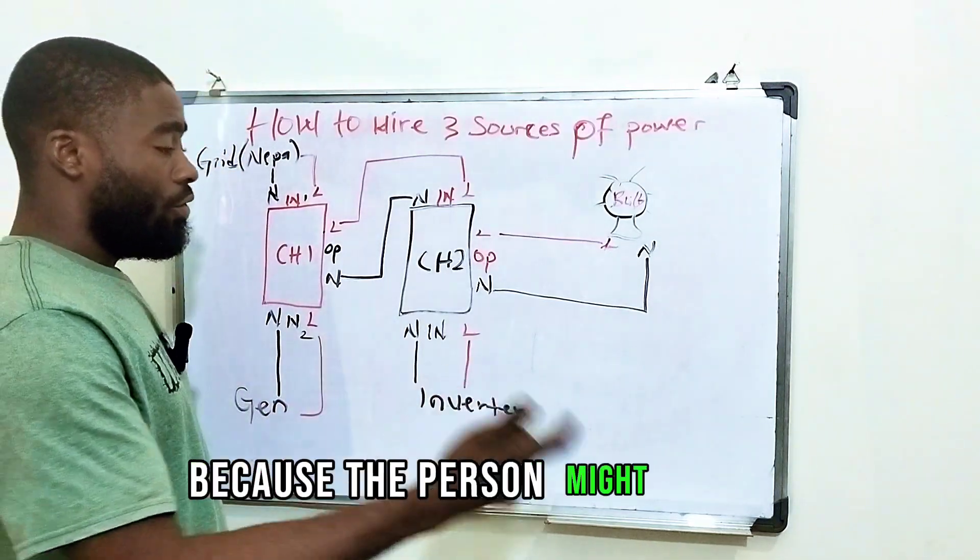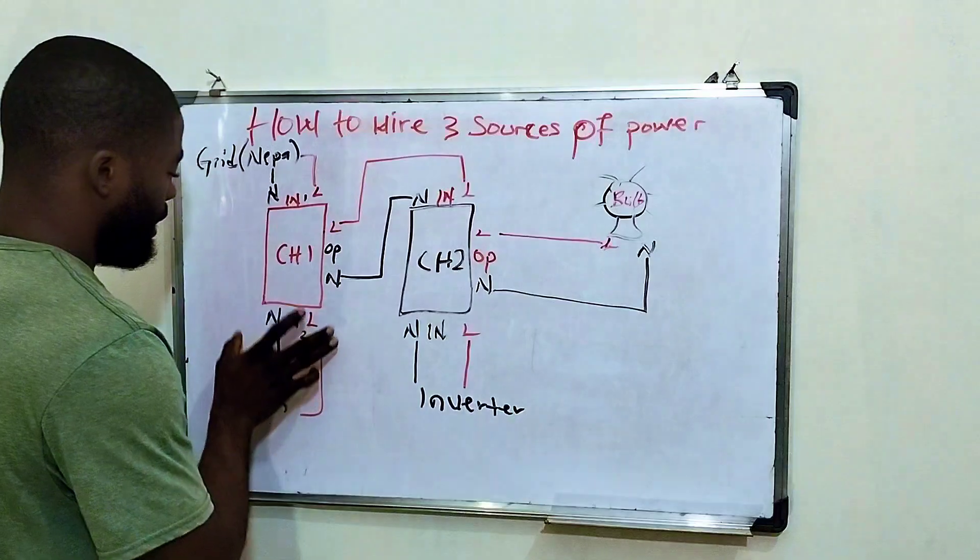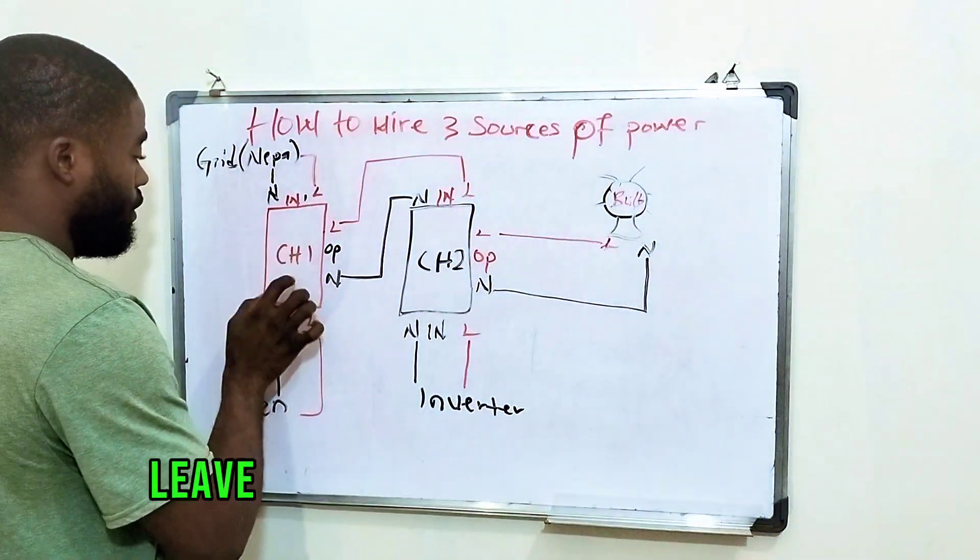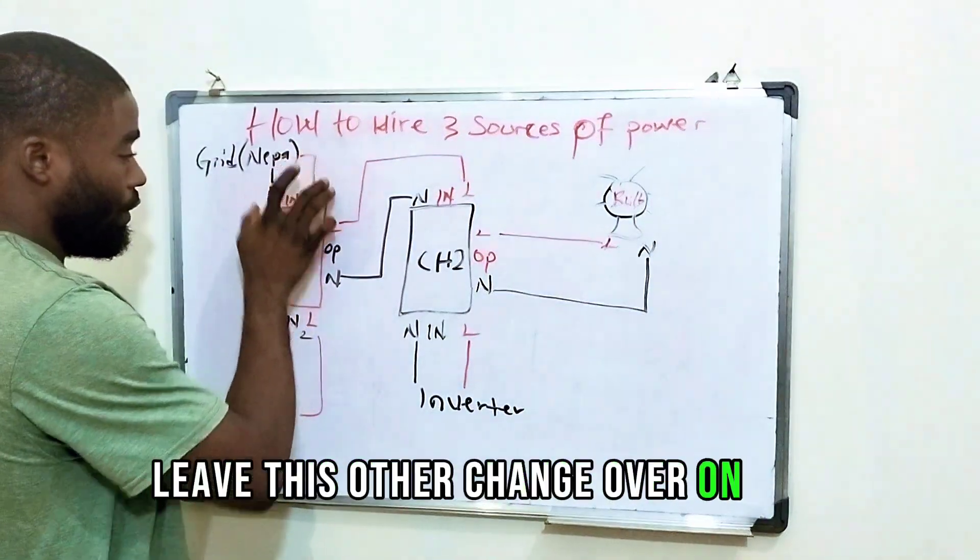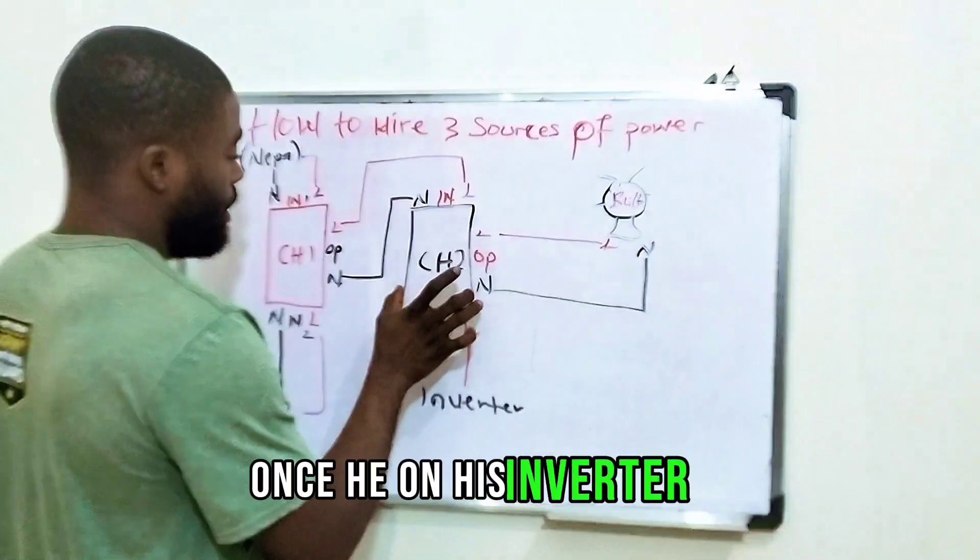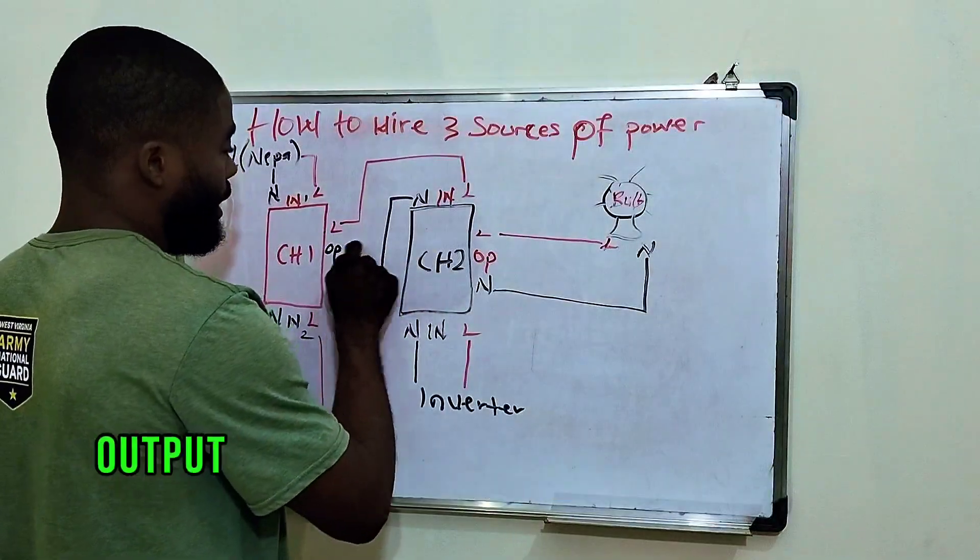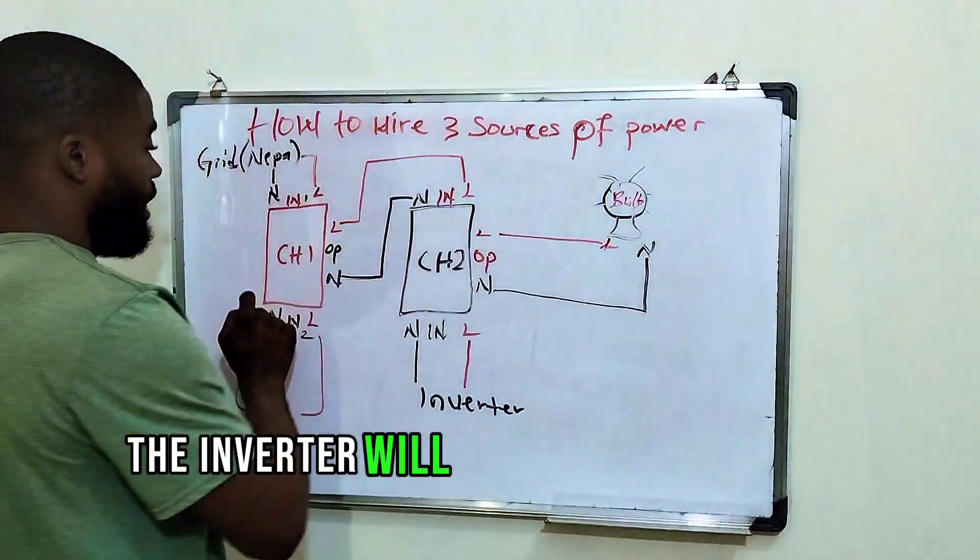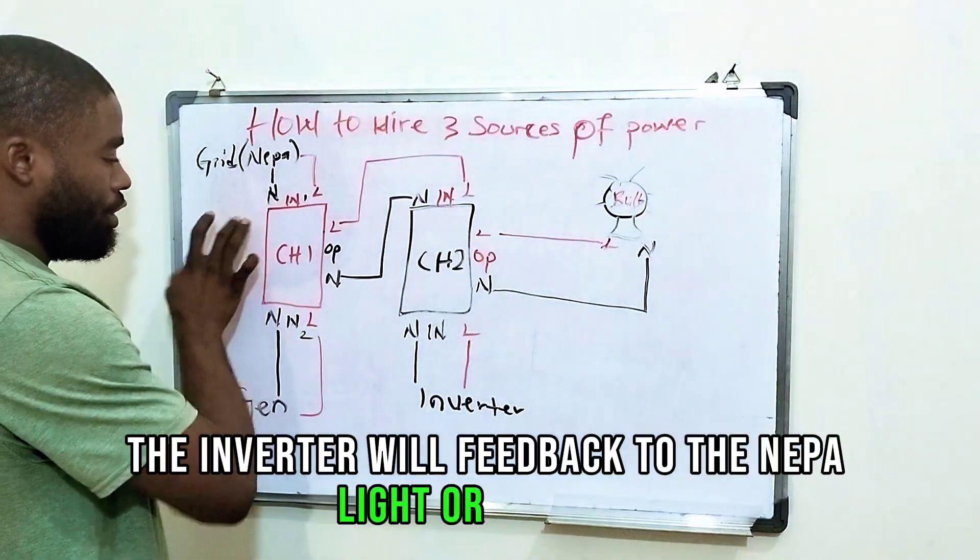Because the person might forget and leave the inverter down here, and then leave that changeover on grid. Once he turns on his inverter, because this output here is connected to the output of this one, the inverter will feed back to the NEPA light or the grid.